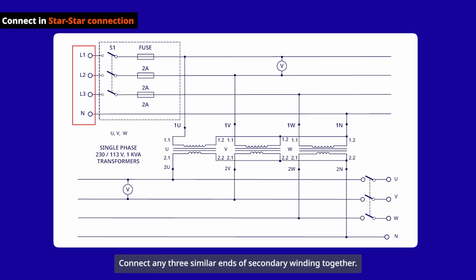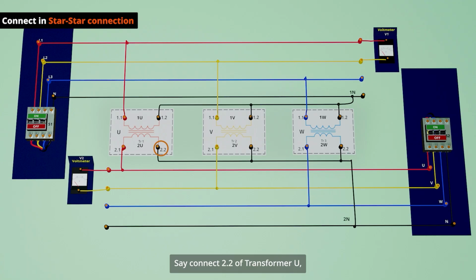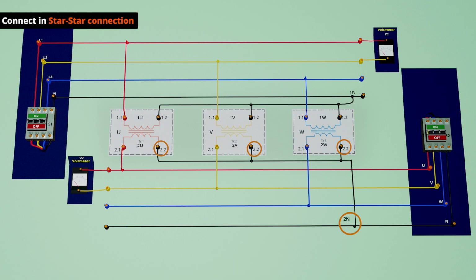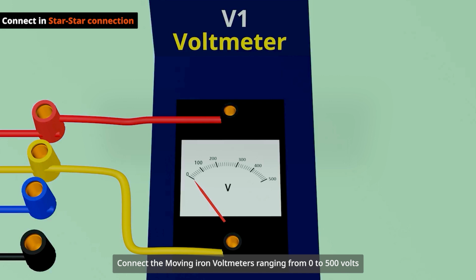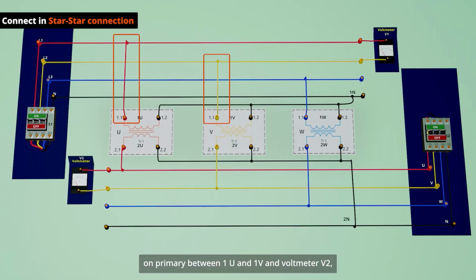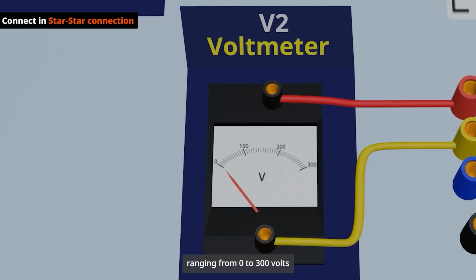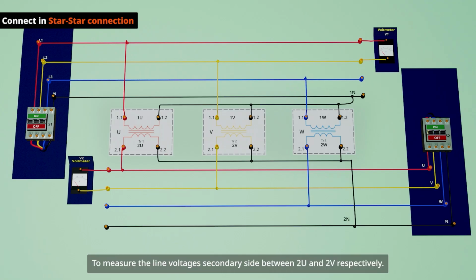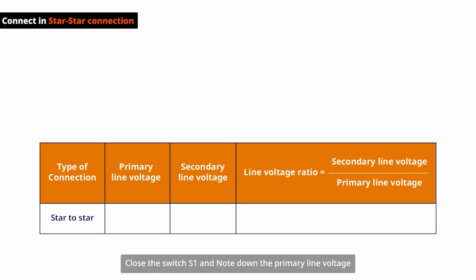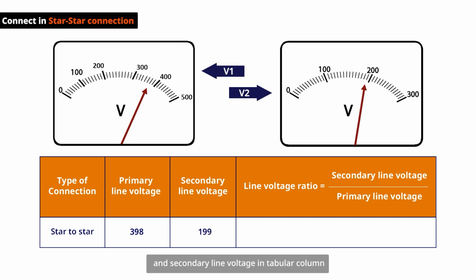Connect any three similar ends of the secondary winding together. Say, connect 2.2 of transformer U, 2.2 of transformer V, and 2.2 of transformer W together and mark the junction as 2N, as shown in the circuit diagram. Connect the moving iron voltmeter V1, ranging from 0 to 500 volts, to measure the line voltage on the primary between 1U and 1V, and voltmeter V2, ranging from 0 to 300 volts, to measure the line voltage on the secondary side between 2U and 2V respectively. Close the switch S1 and note down the primary line voltage and secondary line voltage in a tabular column under star-star connection.